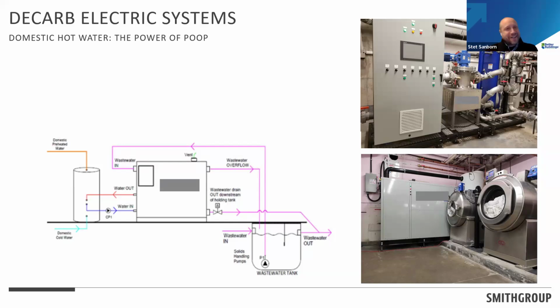The heat pump keeps it segregated, but you get far better performance out of a wastewater heat pump than you would an air source heat pump, especially in cold climates. So if you reference back to that advanced energy design guide, we did all the simulations, we did all the comparisons, and we actually tell you which climate zones work best for each type of heat pump on domestic hot water. So it's a great resource if you haven't heard of these things before. Next slide.